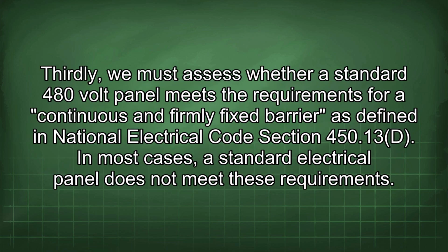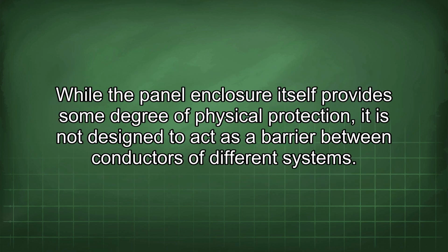Thirdly, we must assess whether a standard 480-volt panel meets the requirements for a continuous and firmly fixed barrier as defined in National Electrical Code Section 450.13d. In most cases, a standard electrical panel does not meet these requirements. While the panel enclosure itself provides some degree of physical protection, it is not designed to act as a barrier between conductors of different systems.